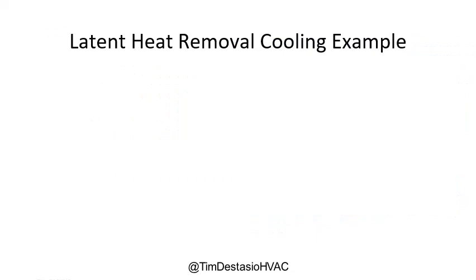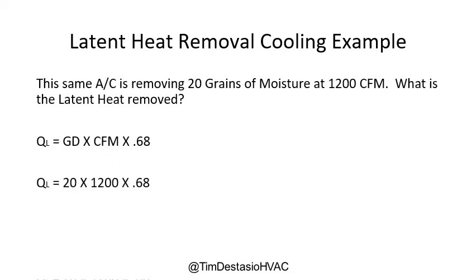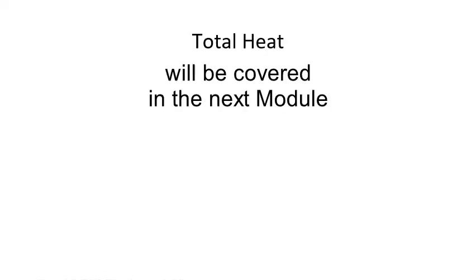Now let's plug these values into the latent heat formula. The air conditioning system is removing 20 grains of moisture at 1,200 CFM. Plugging into the formula — 20 grains difference times 1,200 CFM times 0.68 — we arrive at 16,320 BTUs per hour, or 1.36 tons of latent heat removed. So far we've discussed sensible heat and latent heat, and now we can put those two together to arrive at total heat.